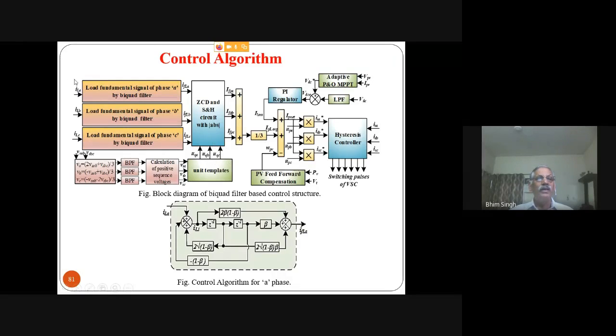Again, we sense the three-phase load current, and we calculate the fundamental current using some kind of filter. From the fundamental and quadrature, these are not phase templates, these are quadrature templates, so we again have a zero crossing detector logic, not a circuit, because it's all in the processor. So we get only the amplitude of the active component of current. Since there may be load unbalance, their values may be different, so you have to add them, because it's amplitude, and divide by 3, so that load balancing can be taken care of. Dividing by 3 means you are calculating per phase.